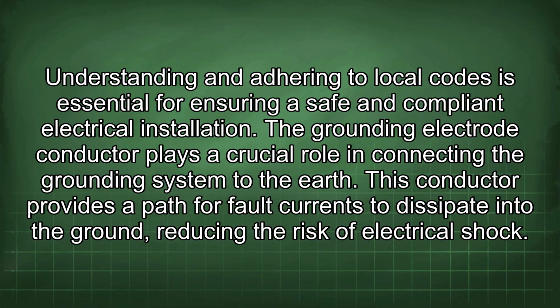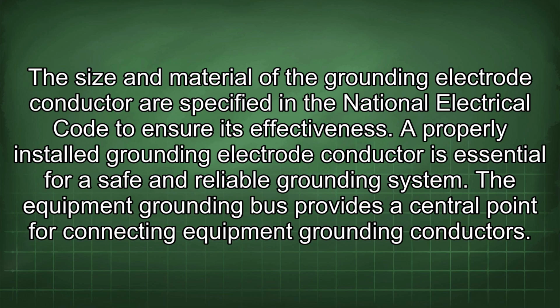The grounding electrode conductor plays a crucial role in connecting the grounding system to the earth. This conductor provides a path for fault currents to dissipate into the ground, reducing the risk of electrical shock. The size and material of the grounding electrode conductor are specified in the National Electrical Code to ensure its effectiveness. A properly installed grounding electrode conductor is essential for a safe and reliable grounding system.